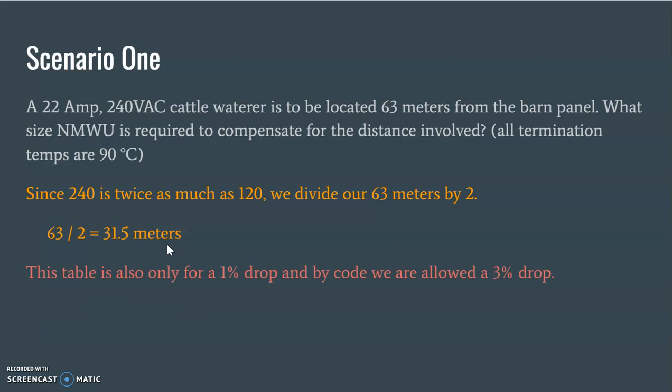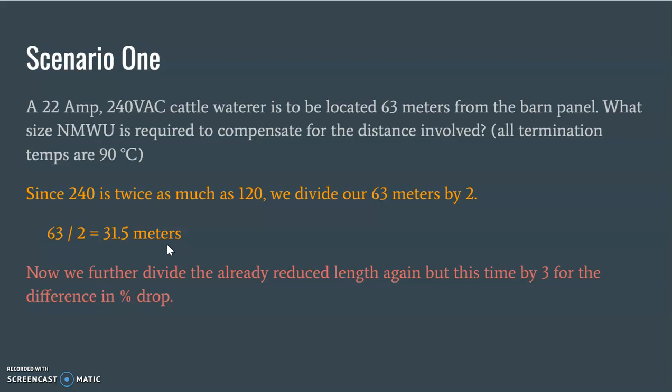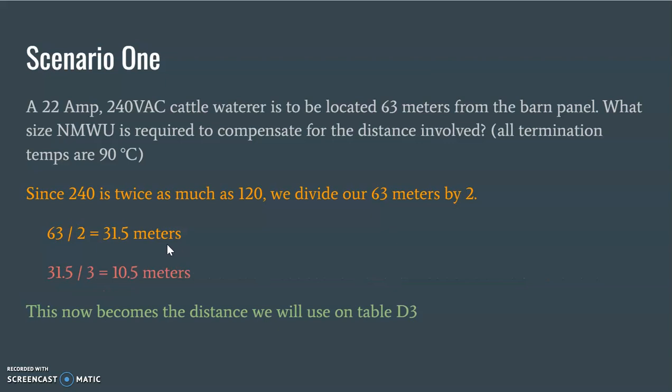But that's not it. We're not done. This table again is only good for a 1% drop. We have, or we're allowed by code, a 3% drop for this branch circuit, which again, being fed out of a panel makes it a branch circuit, and we're allowed a 3% drop. So again, we will reduce that length again, this time by 3 for the percent difference drop. So that's what it's going to look like. So take this already reduced distance here, again, divide it by 3. And so this now becomes the distance on our table that we're going to look for, because we've matched or made our 63 meters fit something that is applicable to Table D3.